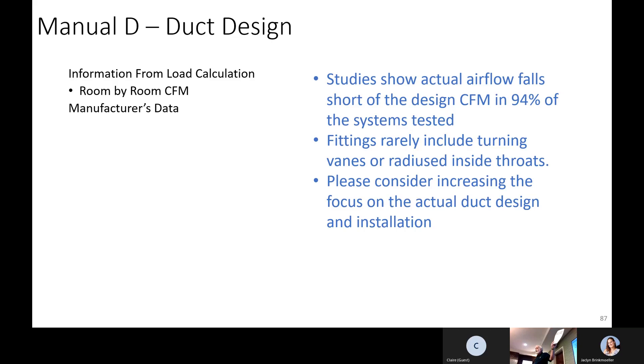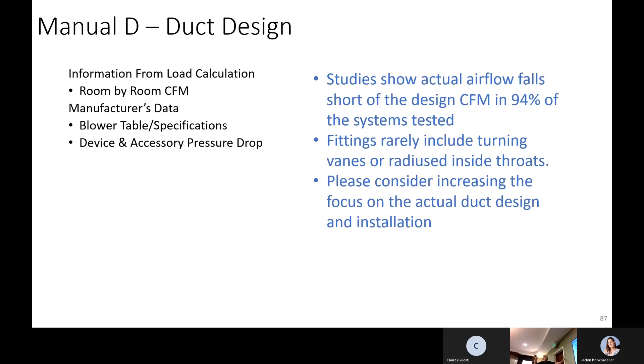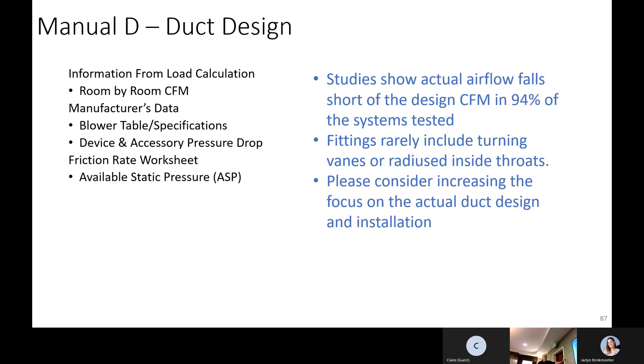From our load calculation we need our room-by-room CFM — and we have that here. We need the manufacturer's blower data, which isn't in there. We need device and accessory pressure drops — things we put in the air stream that restrict airflow: air filters, air conditioning coils, ultraviolet lights, humidifiers that stick into the duct stream. We do a friction rate worksheet to identify those. We look at all the devices we put in, including registers and grilles, and ask — after we put all those devices in, do we have any pressure left for the duct system? Because we're going to have losses in the duct system.